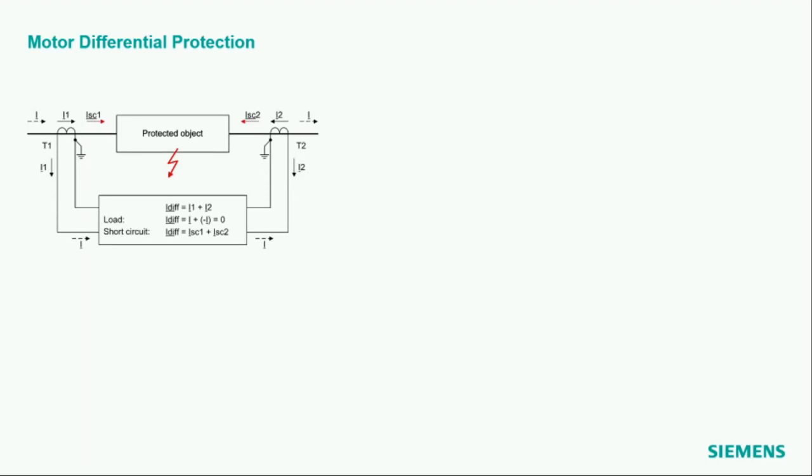So how does our differential protection function work? First, it is like the transformer differential protection function. It's a subset of that function. We took that function and took out all the stuff we don't need for motors, for example the vector shift compensation, or the star point compensation, the zero sequence current elimination. This is all not required here because we have just a current going in and out, and we have a galvanically connected motor wiring between both. So all this nice stuff we have with the transformer differential protection we don't have here for the motor protection.